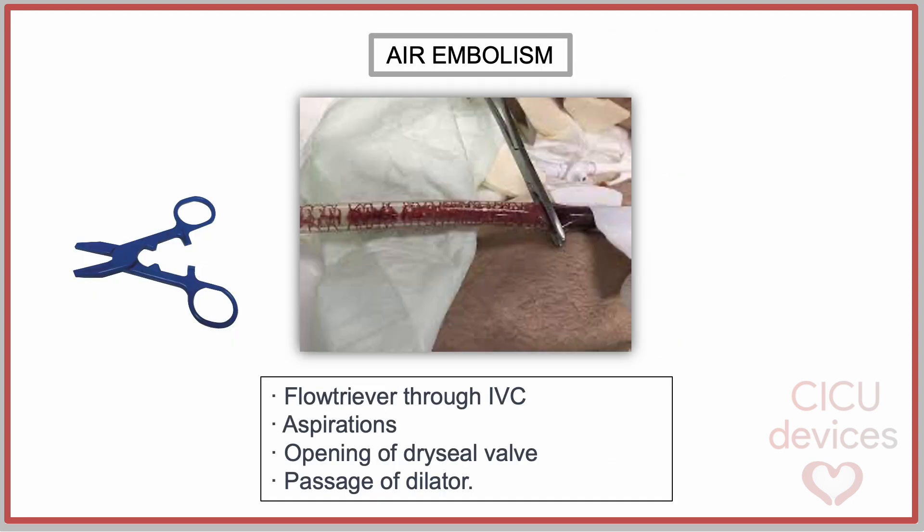Air Embolism: The advice to prevent this event is to clamp or decrease ECMO flow to 1L per minute during the following steps: FlowTriever passage through the inferior vena cava, successive aspirations through the catheter, and opening of the dry seal valve and passage of the dilator.